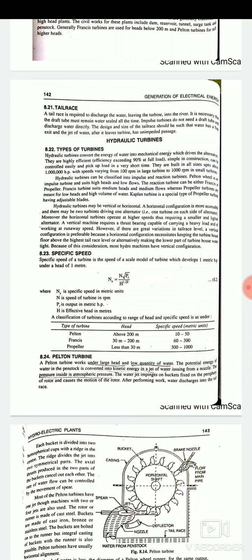Next is tailrace. A tailrace is required to discharge the water leaving the turbine into the river. It is necessary that the draft tube must remain water sealed all the time. Impulse turbines do not need a draft tube and discharge water directly. The design and size of the tailrace should be such that water has a free exit and the jet of water after it leaves turbine has unimpeded passage. So this is about tailrace. Next is hydraulic turbines which are used in the hydroelectric power plants.